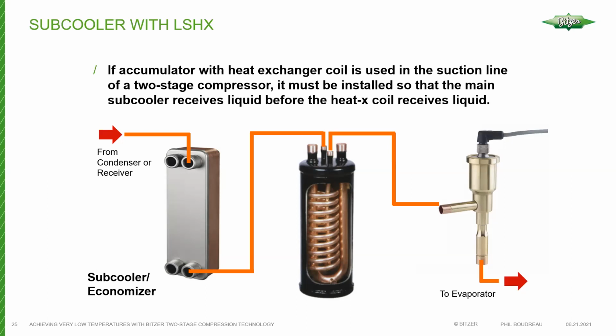In a situation where a suction accumulator may be used with a heat exchanger or boil out coil, as they're sometimes called, you want to do this after the brazed plate heat exchanger that's used for subcooling and interstage cooling. Because the idea is the subcooler, we want to load that valve up as much as possible. What this does is promote as much flow as the interstage needs to keep that compressor down to BITZER's required superheat for the application. So generally, I wouldn't expect a suction accumulator with a boil out coil to do tons of work, but we want to take that off the table. Any additional subcooling that you do to that refrigerant, you want to do it after the brazed plate heat exchanger. Let the interstage do its thing, and then you can provide that type of accumulator afterwards if you want. So your liquid loop in that heat exchanger essentially would be placed between the brazed plate heat exchanger outlet and the inlet to the expansion valve.